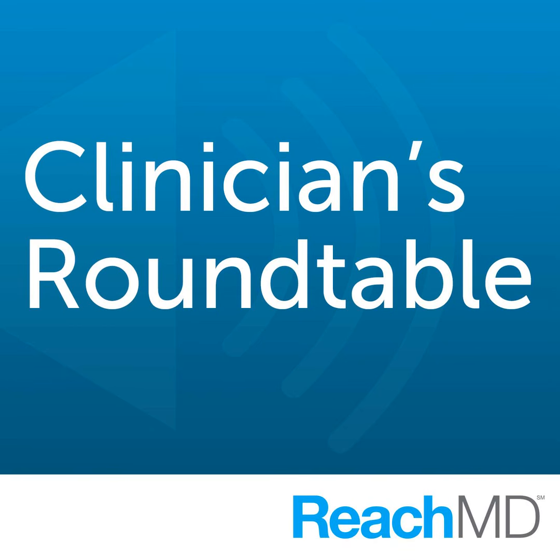So, even when a pump is programmed correctly and everything's working as it should, the amount of medication a patient actually receives can still be affected by a few technical factors like dead volume, medication left behind in the tubing, and titration effects. So, Dr. Ubanyionwu, what exactly happens in each of those cases and why do they matter clinically?